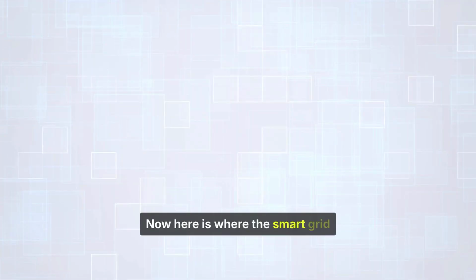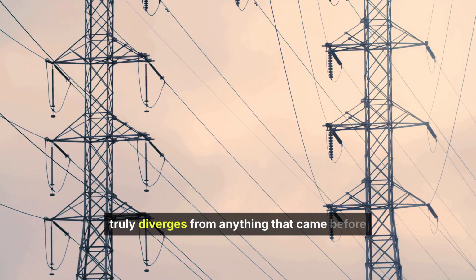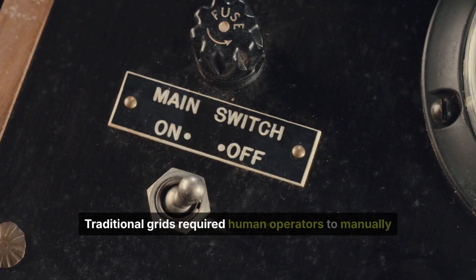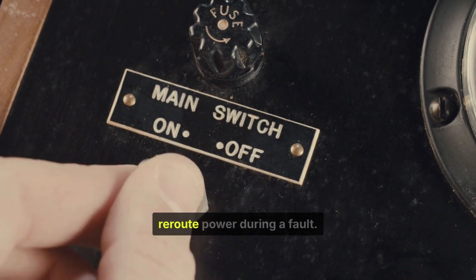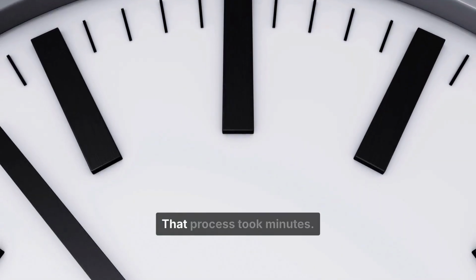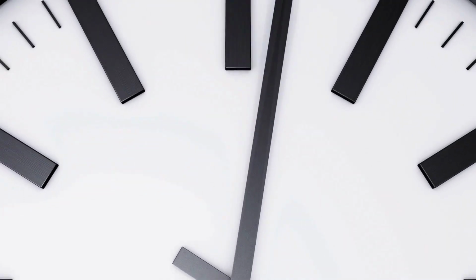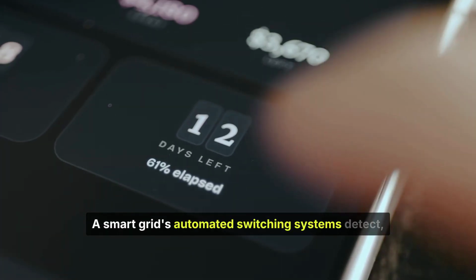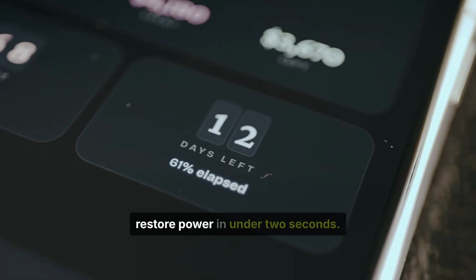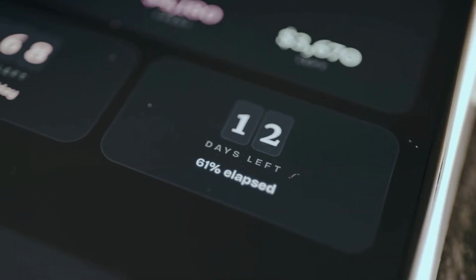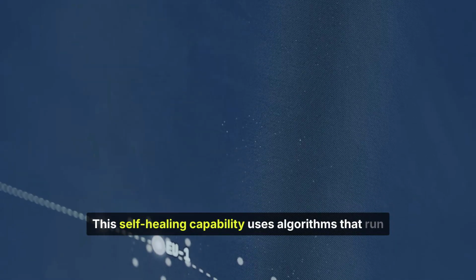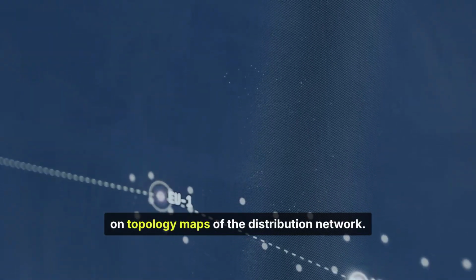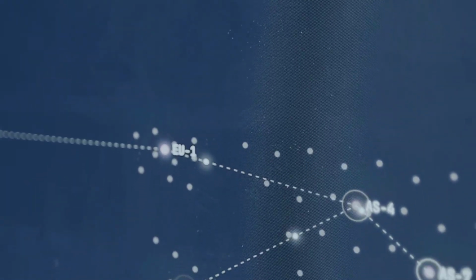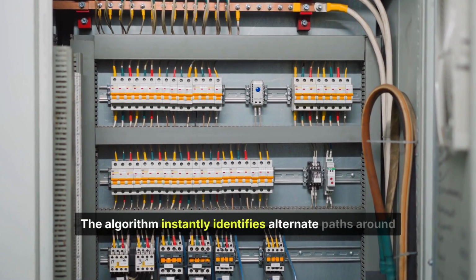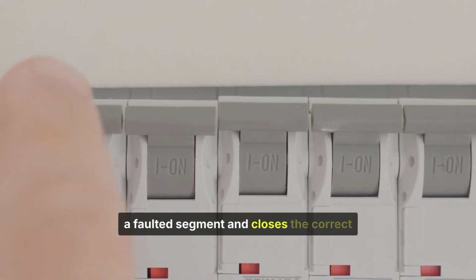Now here's where the smart grid truly diverges from anything that came before it. Traditional grids required human operators to manually reroute power during a fault. That process took minutes. A smart grid's automated switching systems detect, isolate, and restore power in under 2 seconds. This self-healing capability uses algorithms that run on topology maps of the distribution network. The algorithm instantly identifies alternate paths around the faulted segment and closes the correct switches automatically.